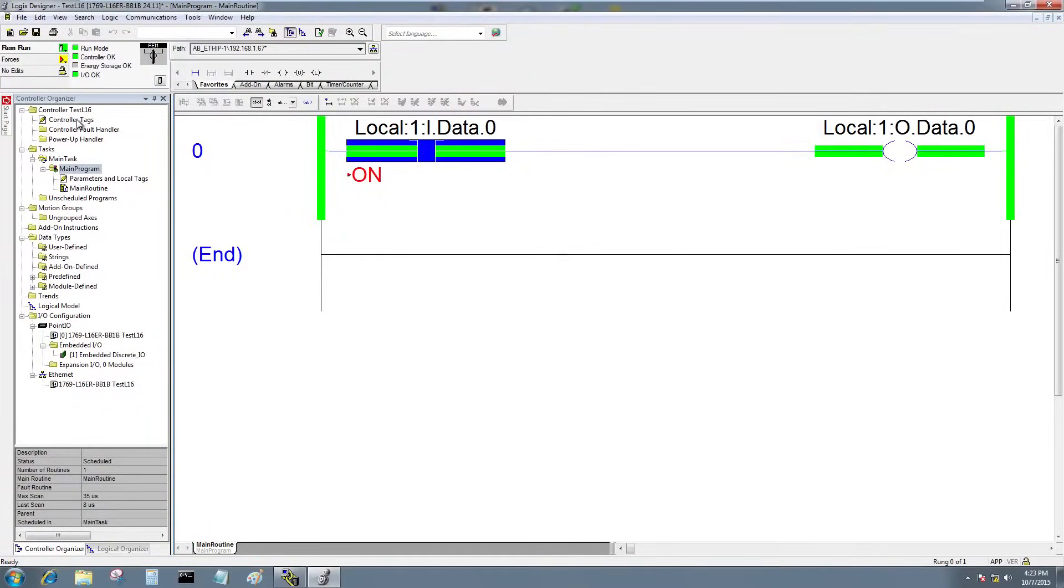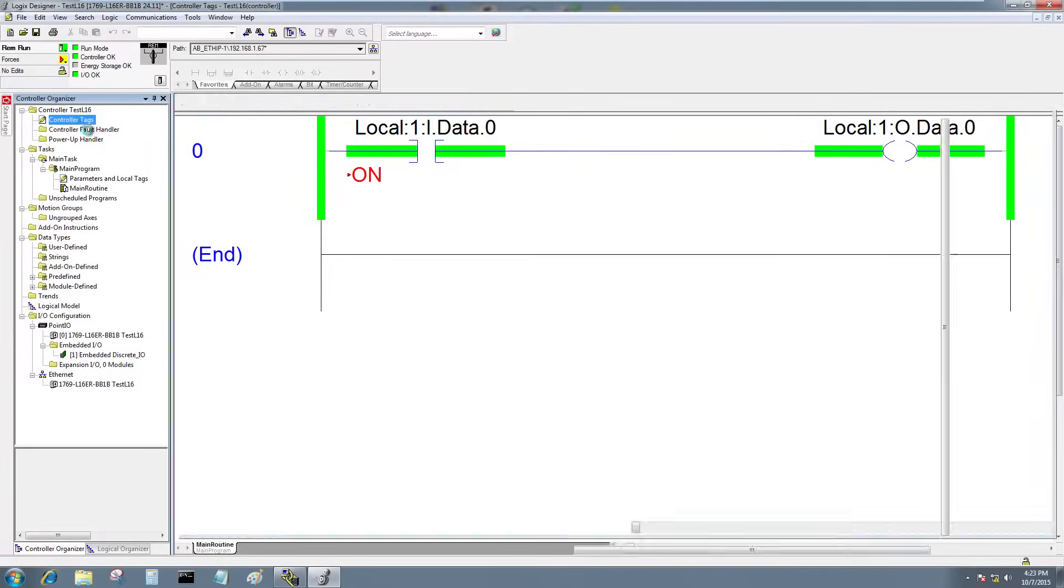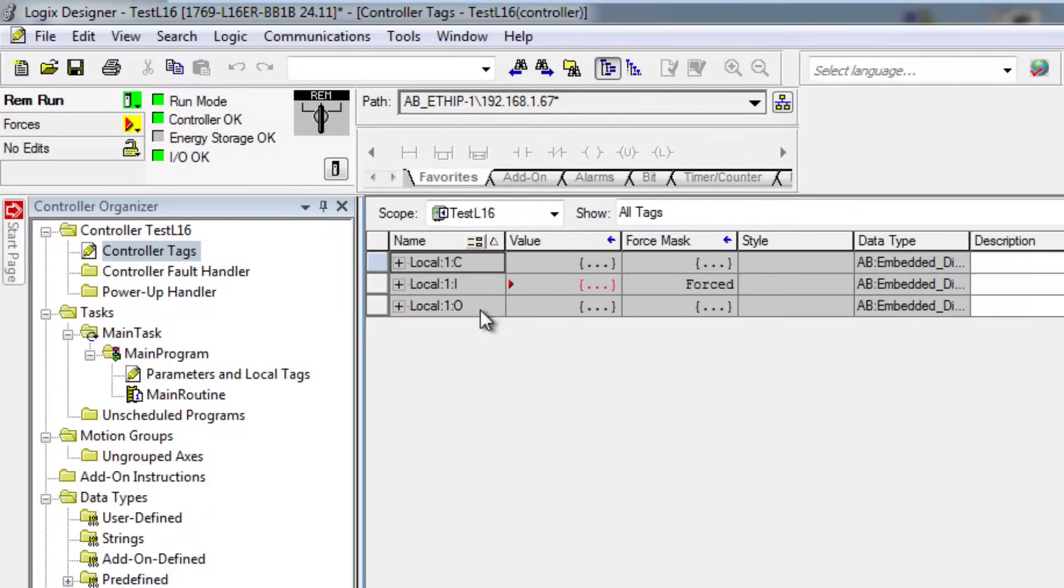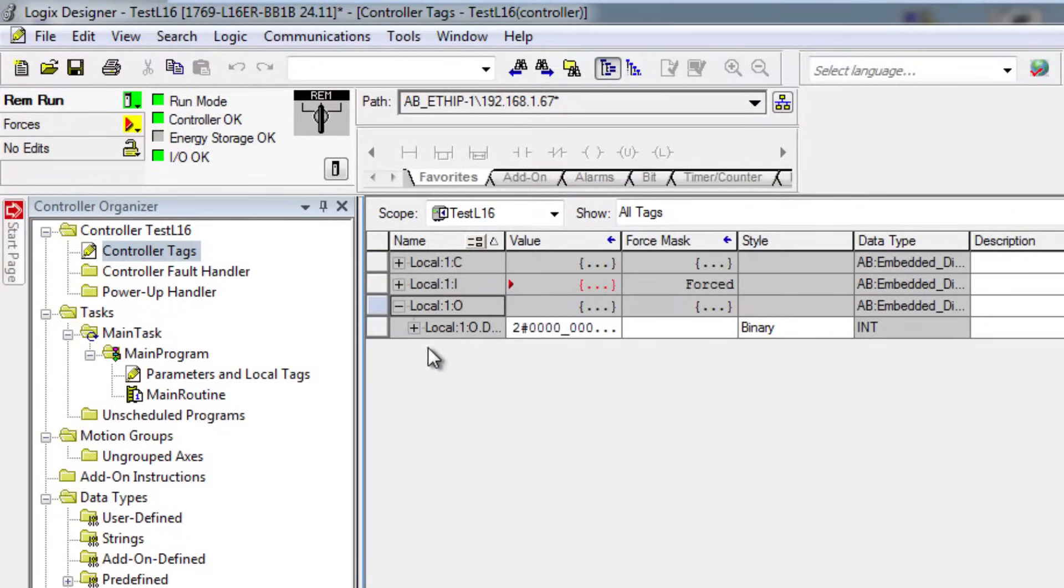If I want to turn on another output, just because it's not in the program yet is not a big deal. I can actually go to the controller tags and go to the local outputs.